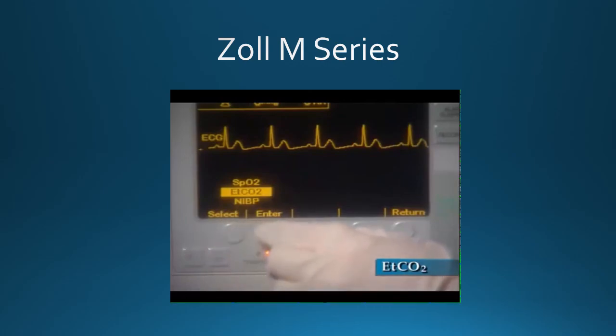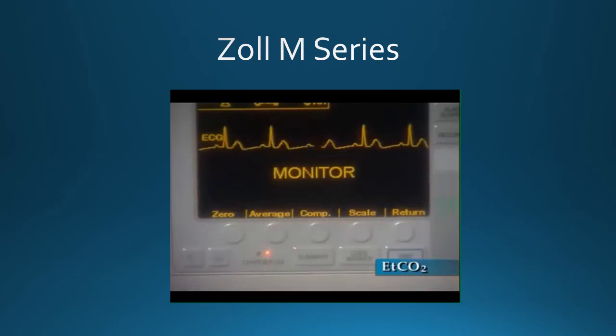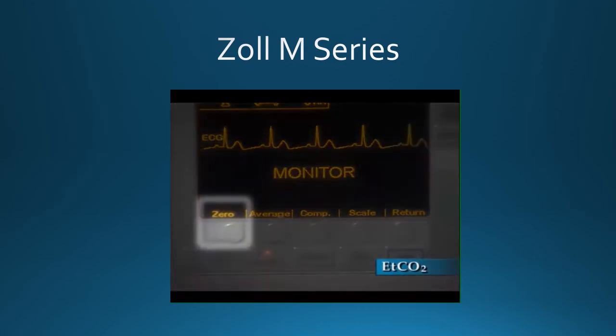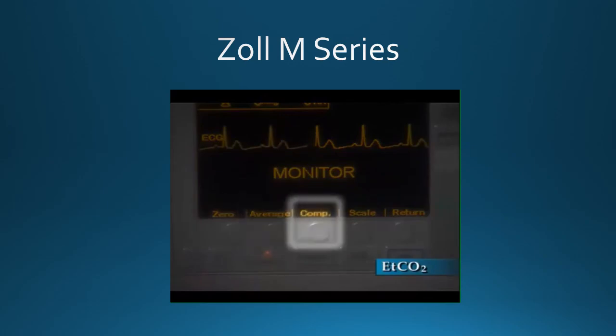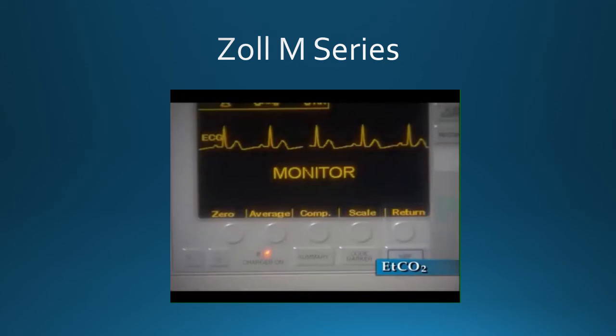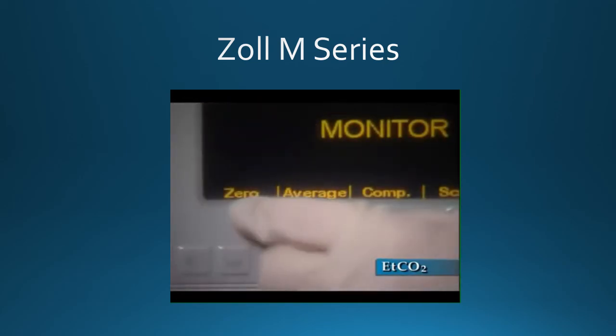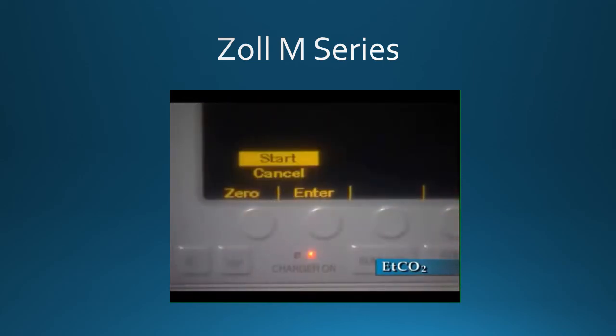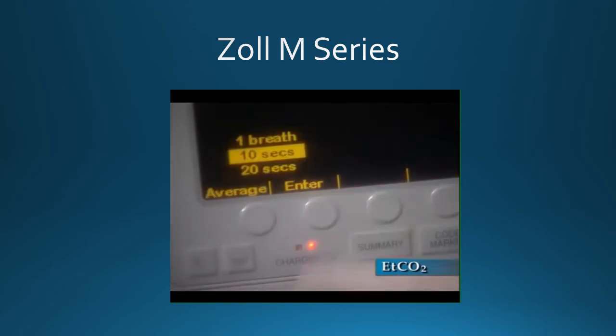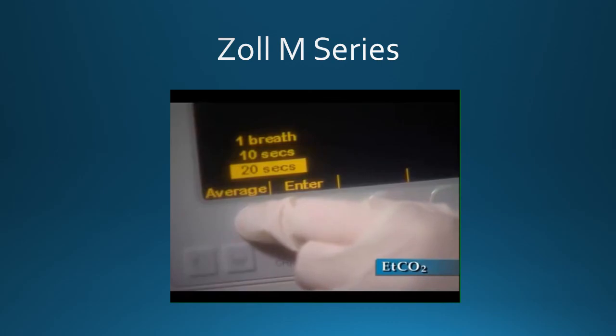Selecting the EtCO2 parameter causes the following soft keys to appear: 0, Average, Compensation, Scale, and Return. The Zero soft key allows the user to begin the process of zeroing the adapter. The Average soft key provides 3 different time periods over which the highest EtCO2 values are averaged: 10 seconds, 20 seconds, or 1 breath.